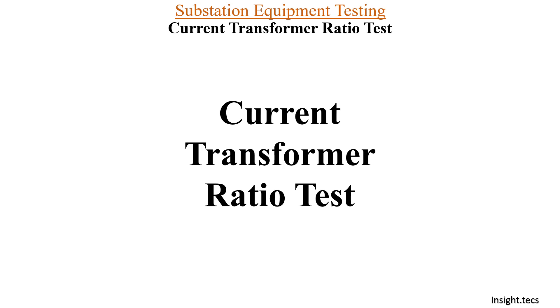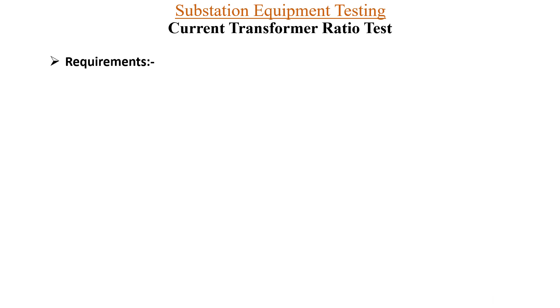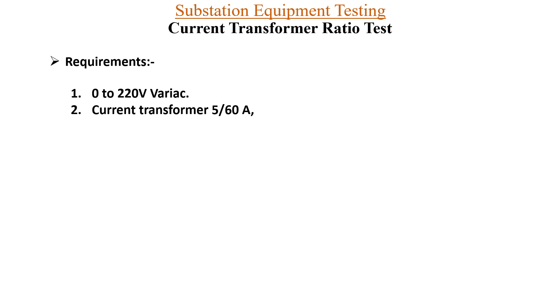Let us see how the current transformer ratio test is done and why this kind of test is required on the CT. The requirements to perform the CT ratio test are: first, a variac between 0 to 220 volts; second, a current transformer that can convert 5 amperes to 60 amperes or above; extension wires; and a clip-on meter.